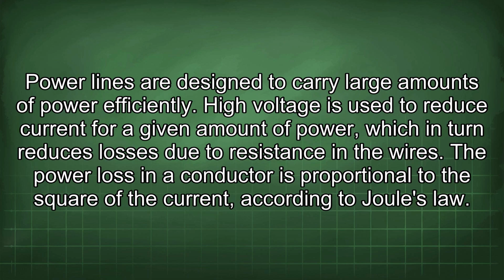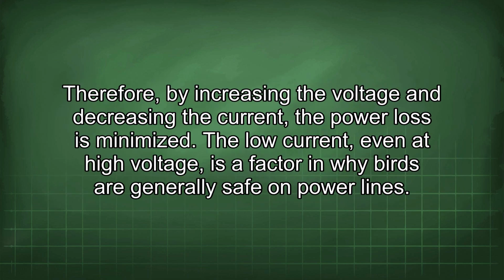Power lines are designed to carry large amounts of power efficiently. High voltage is used to reduce current for a given amount of power, which in turn reduces losses due to resistance in the wires. The power loss in a conductor is proportional to the square of the current according to Joule's law. Therefore, by increasing the voltage and decreasing the current, the power loss is minimized. The low current, even at high voltage, is a factor in why birds are generally safe on power lines.